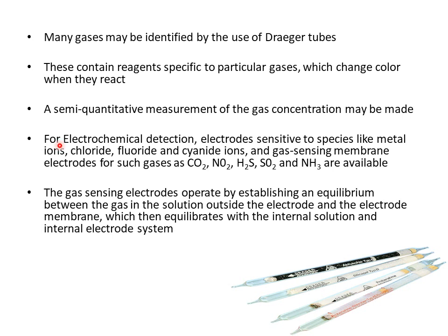For electrochemical detection, electrodes sensitive to species like metal ions, chlorides, fluorides, and cyanide ions are available. Gas-sensing membrane electrodes are available for gases such as carbon dioxide, nitrogen dioxide, hydrogen sulfide, sulfur dioxide, and ammonia. These gas-sensing electrodes operate by establishing an equilibrium between the gas in solution outside the electrode and the electrode membrane, which then equilibrates with the internal solution and internal electrode system.